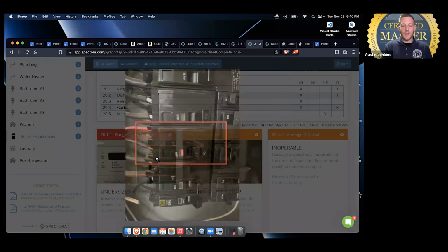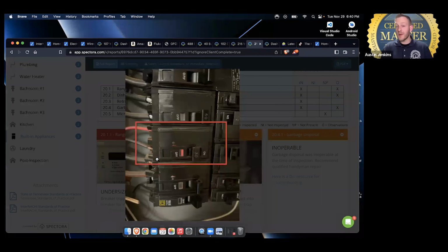So I go to the electrical panel, and it turns out it's only on a 30 amp breaker. Most stoves, if they're electric, top and the actual oven itself, are usually on a 50 amp breaker. So you can see we have a 30 amp breaker with 10-3 wiring. That's one thing I wrote up, and this actually damaged that breaker.